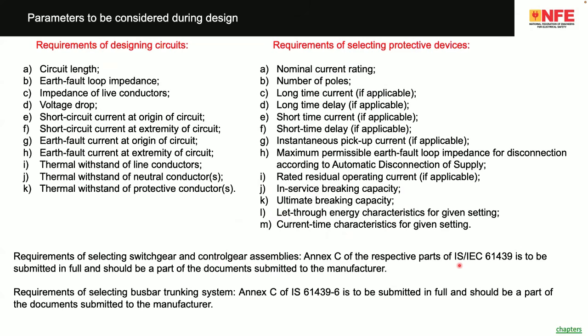Example, if you are buying switchgear and controlgear assemblies, meaning the electrical panels, legally you are supposed to use electrical panels which are in compliance with IS IEC 61439. Now, if you look into this particular standard, there is an annex, and Annex C explains what kind of information is required to make a panel board. Similarly, for the busbar trunking system, Annex C of the standard explains what kind of requirements there are to make a good quality busbar trunking system.